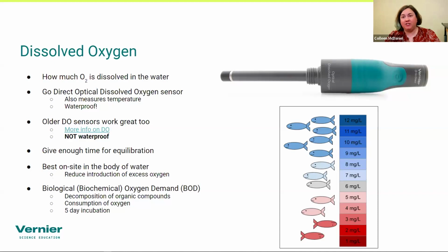Again, like pH and temperature, with dissolved oxygen you want to make sure you give enough time for calibration and equilibrium to take place. I get a lot of questions like 'it's not reading right, it's not reading right,' but if you're looking at a water sample that's a lot colder or warmer than your surroundings, it can take 3 to 5 minutes in some cases for the sensor to reach equilibrium and give a proper reading.